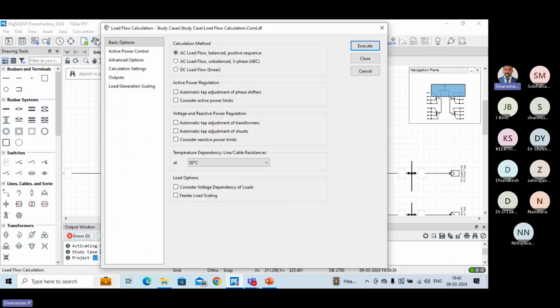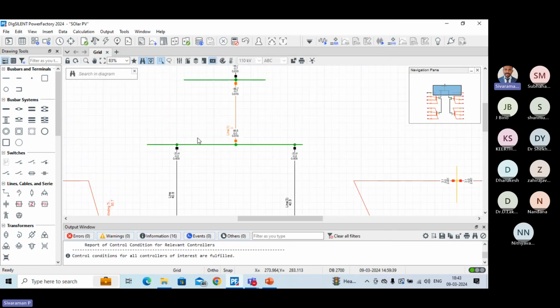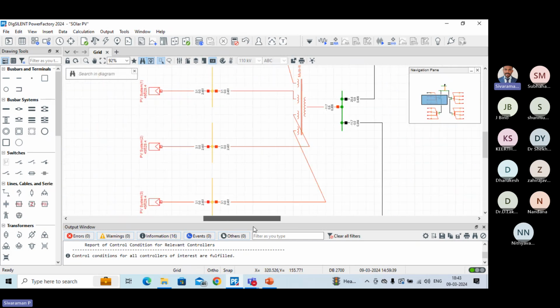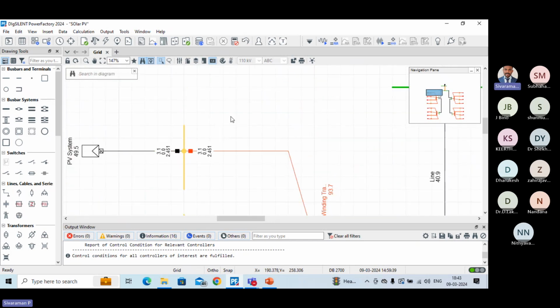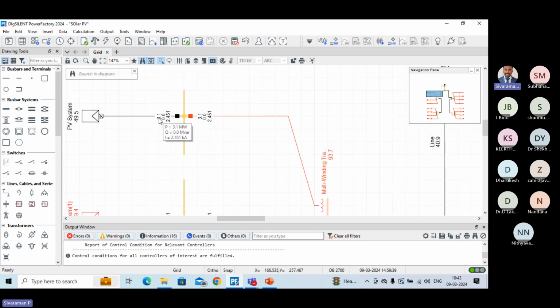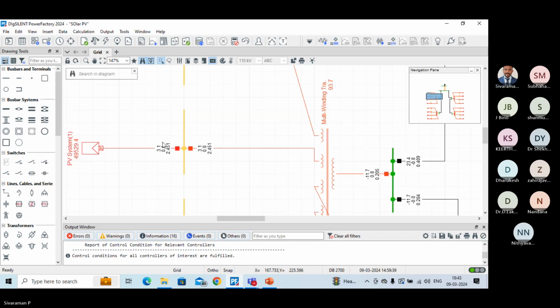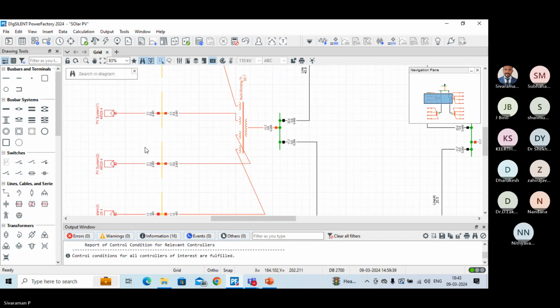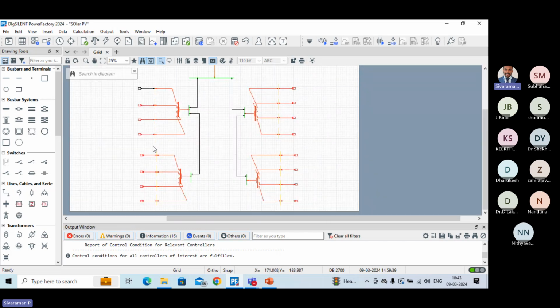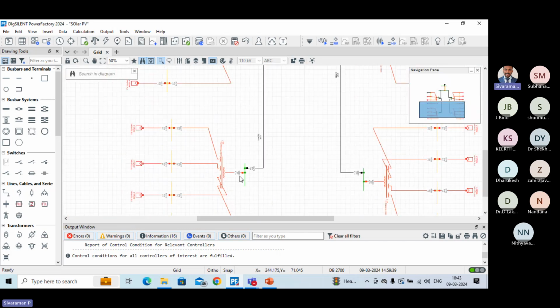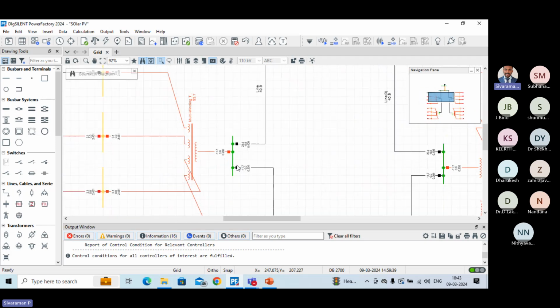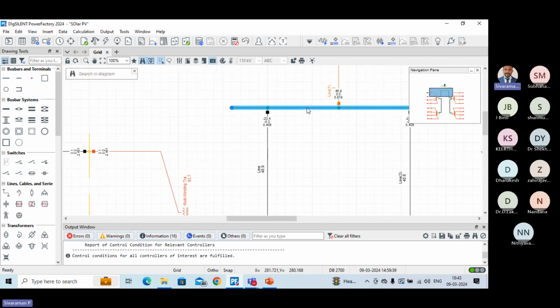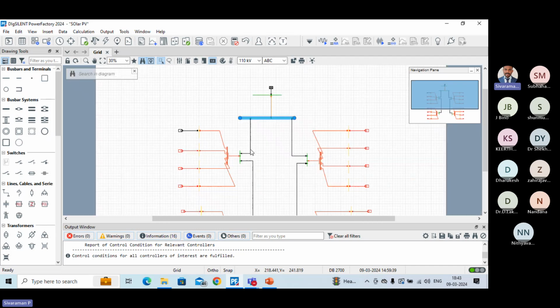Now I am running the load flow analysis. Maybe electrical engineers who studied power system analysis know what load flow analysis is. So now I am executing the load flow analysis. You can see that at this moment each inverter is delivering 3.125 megawatt of active power. One inverter block is connected to another inverter block, and this block is connected to the main MV bus. It is a radial type of connection.